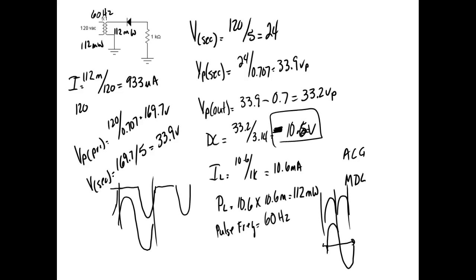But if you put a half-wave rectifier on there and lose one of your diodes, your DC motor is going to run at half the speed of what you're expecting. That's one good indication, because the output voltage will be real low. So if you measure with a meter and you're expecting minus 10.6 but you're getting minus 5 point something, odds are one of your diodes is gone.